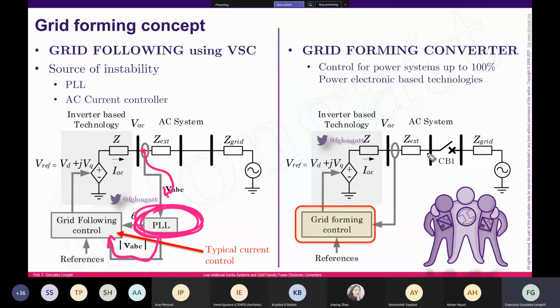And there is another control, the grid forming. Grid forming tries to imitate, tries to mimic, tries to create a synchronous machine using a power converter. That is the most basic way I can explain a grid forming converter: basically a voltage source, enabled with control loops.